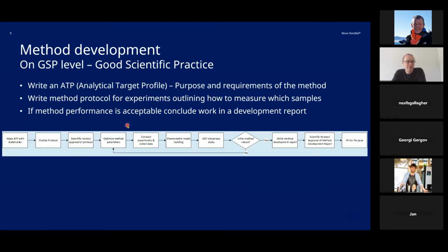If the software supports the expiration of a background, then we can just write in the software that after 1 hour you cannot start more measurements. If the software is not very GMP ready, then we need to have protocols establishing that humans should ensure that this is not the case.